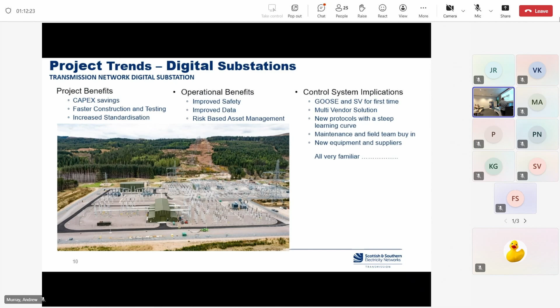The control system implications are very familiar to when we first moved from hardwired to 61850. We've got Goose and SVs for the first time, a multi-vendor solution, and new products with a steep learning curve. All of this is what we learned from first deploying 61850 as MMS only, now with new equipment and suppliers to bring us up to date with IEDs that can perform digital functions.